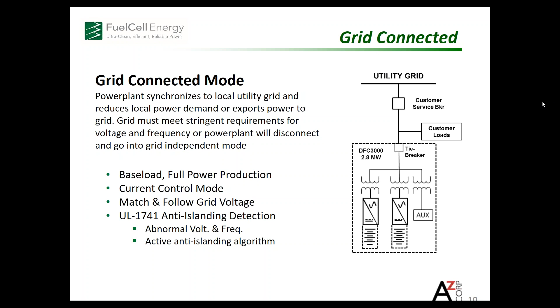On the next slide, we're going to show our microgrid mode, and that shows the tiebreaker there is going to open, and we will provide power to the customer's loads after a brief interruption in the drop and pickup scheme, as I mentioned. Very often, we will equip this configuration with a small gas or diesel genset that allows for the fuel cell to black start in the event that the fuel cell is down for maintenance when the grid goes away. A highly unlikely eventuality, but occasionally, just to get that extra security of secure power, we will employ a small genset to black start that fuel cell plant.